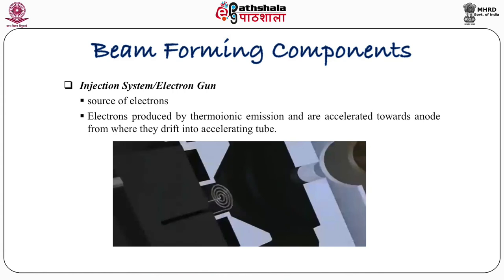The injection system, or electron gun, is the source of electrons. Electrons are produced by thermionic emission and are accelerated towards the anode, from where they drift into the accelerating tube. This is the simple structure of the electron gun. Thermionic emission is produced by giving some voltage and current, and electrons come out. They are accelerated by the anode and approximately 50 keV energy electrons are generated from this electron gun, then injected into the accelerating tube.